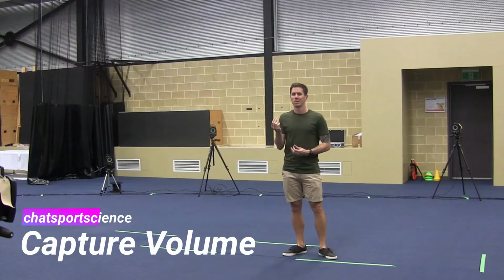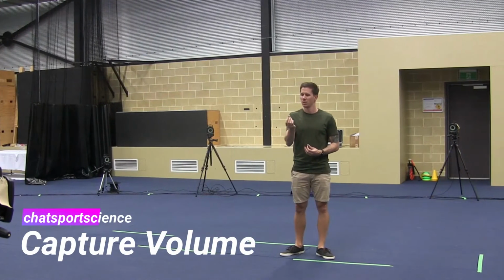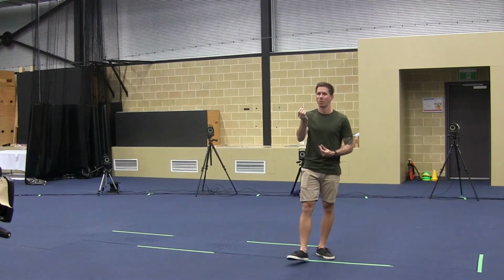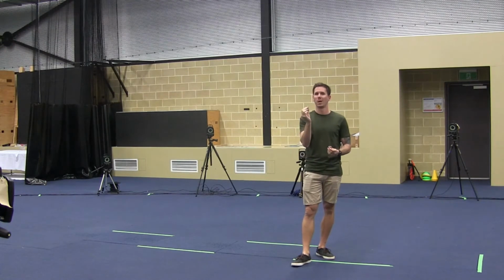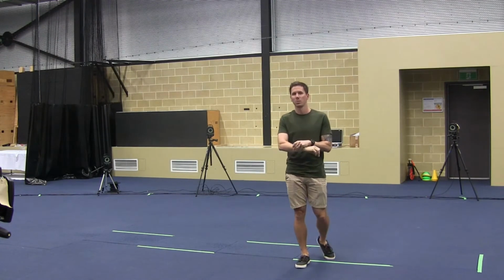Alright guys, up next we're going to look at Vicon camera setup. One of the primary things to consider when placing your cameras is to ensure that at least 2 cameras at any one time are going to be able to see the reflective markers that you're going to be placing on the specific anatomical landmarks.